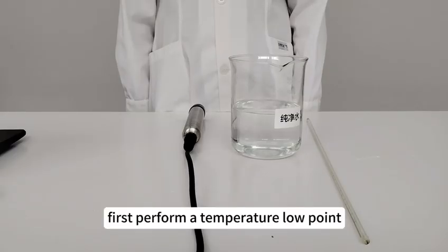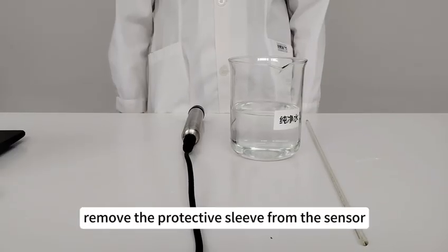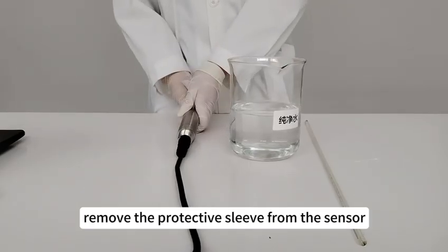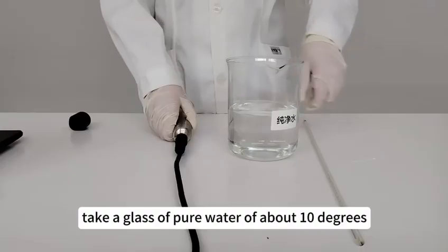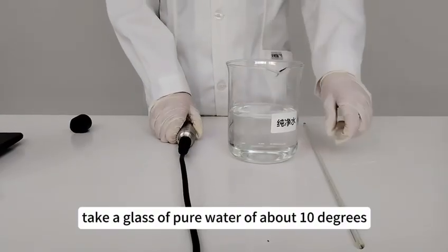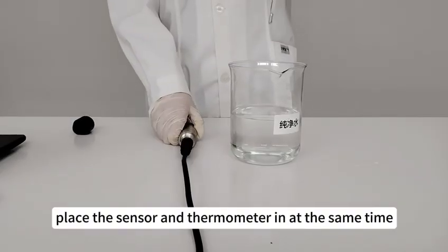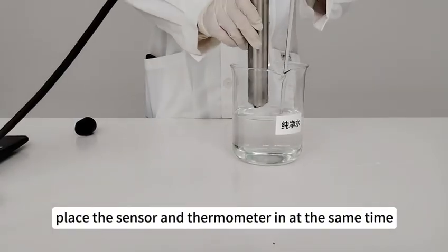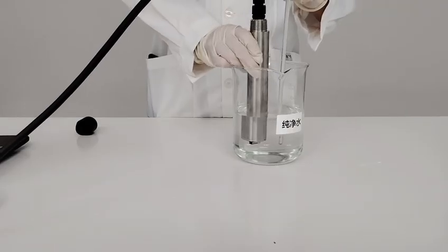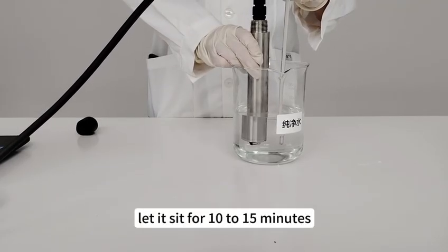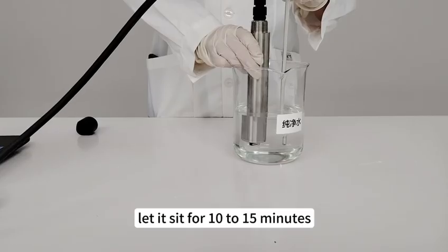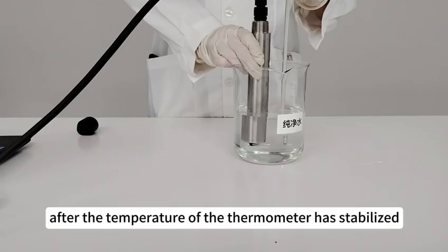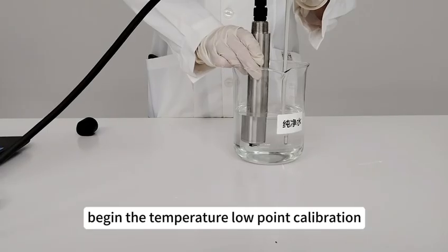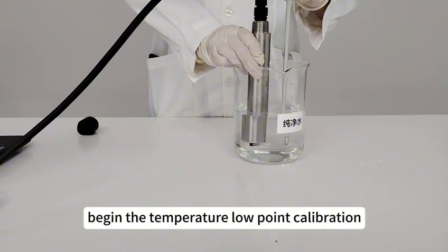First, perform a temperature low point calibration. Remove the protective sleeve from the sensor. Take a glass of pure water of about 10 degrees. Place the sensor and thermometer in at the same time. Let it sit for 10 to 15 minutes. After the temperature of the thermometer has stabilized, begin the temperature low point calibration.